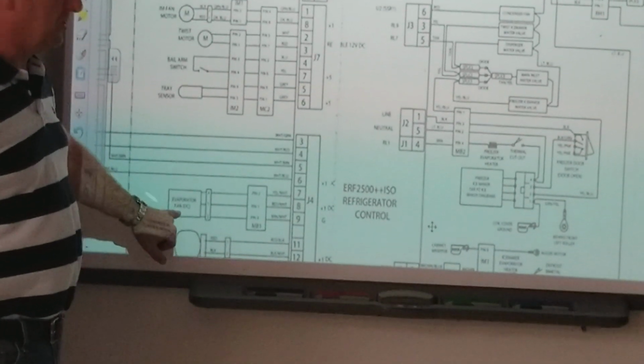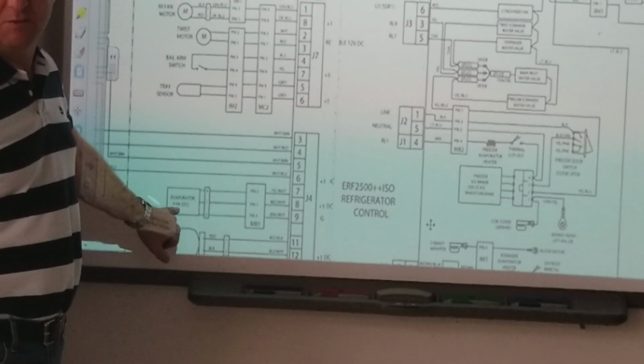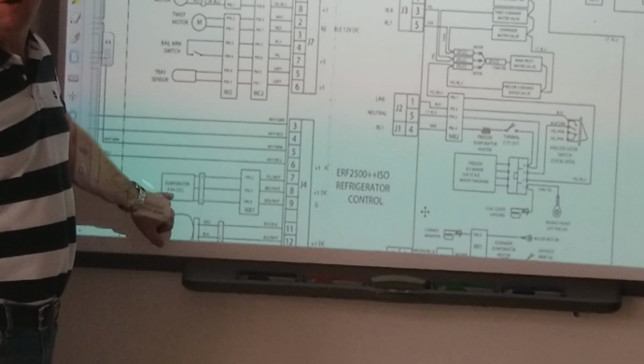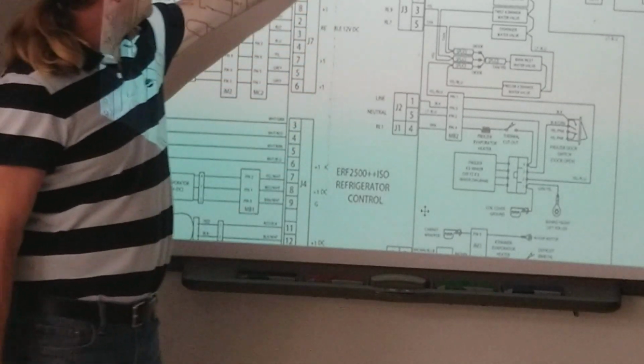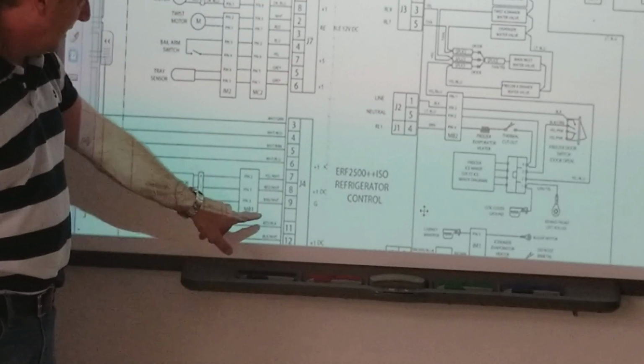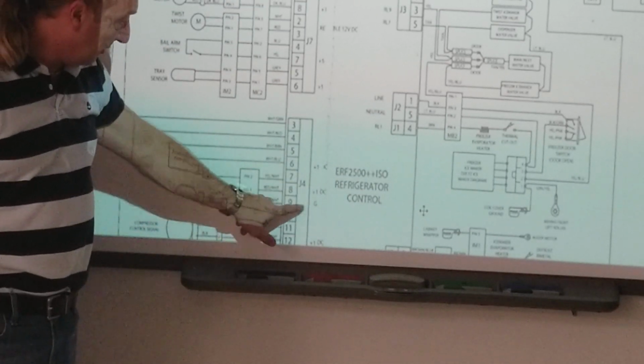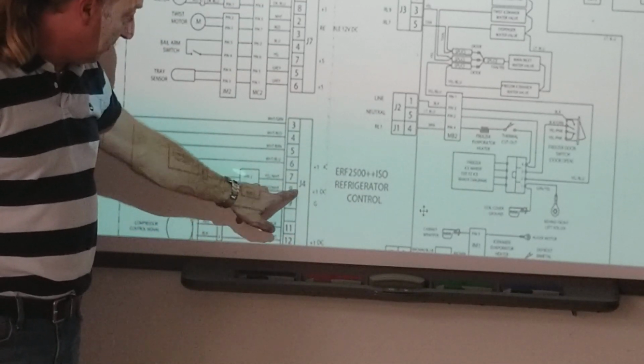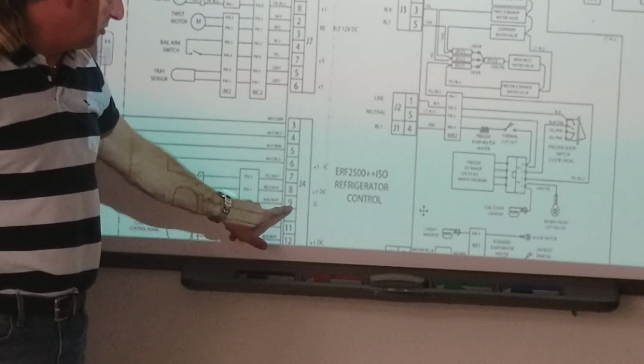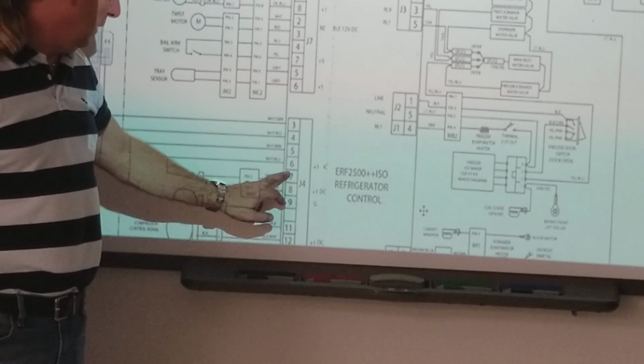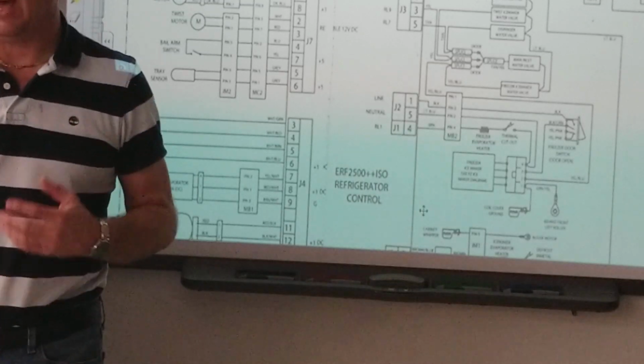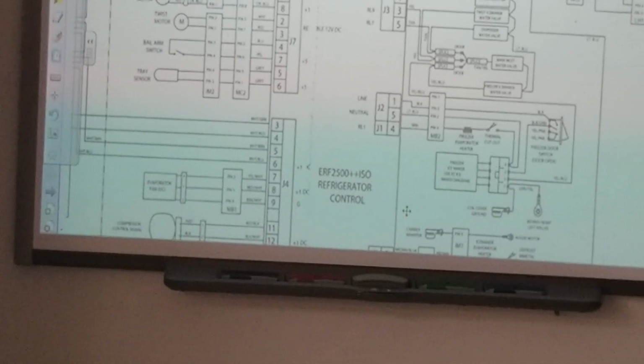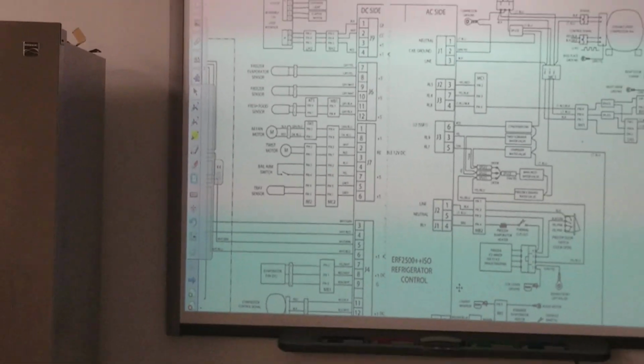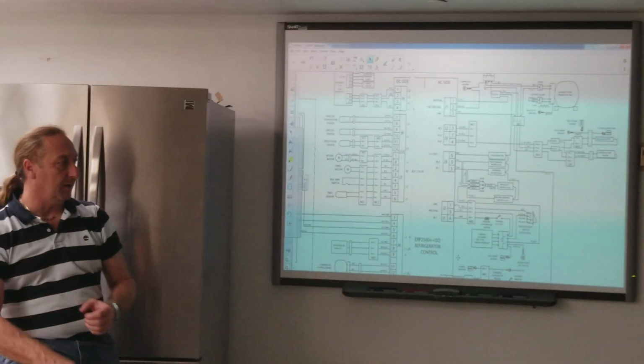Is this evaporator fan AC or DC voltage? DC, because it's on the DC volt side. Look at these wires here: this is plus voltage, number 8, and number 9 is ground, so we have 3 wires. With a DC volt fan we have a power wire and a ground wire, just like a battery, a plus and a minus.